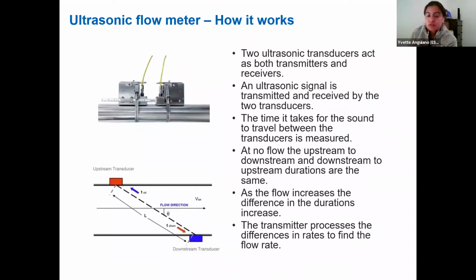So the way that these work is that there are two transducers located upstream and downstream of the pipe, and it sends ultrasonic waves through the fluid. It's measuring the amount of time that it takes to go from one transducer to the other. So if there was no flow going through this pipe, the time that it would take to go from the transducer upstream to downstream and downstream back to upstream would be the same. But if there is flow, then there's a difference in the duration of those signals going back and forth. And the device is processing that difference in the duration and determining the flow rate from that. I won't dig deeper into the explanation of ultrasonic waves, but feel free to dig deeper to get a better understanding of how that works.